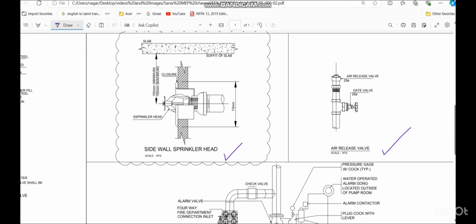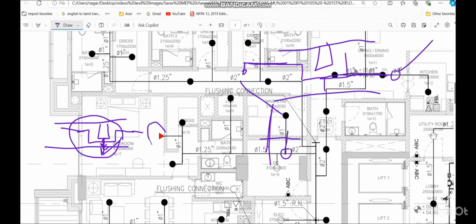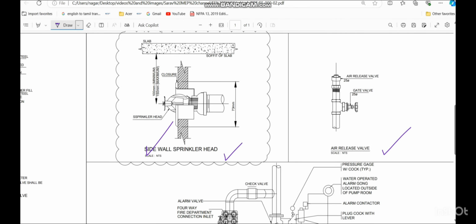Then coming to the next one, we have sidewall sprinkler installation. So in our project, we have sidewall sprinkler. As I told, if for each bedroom we don't have the ceiling, so there we have provided the sidewall sprinkler in the wall. So coming to the sidewall sprinkler, the rule for this like this, you can see the slab. So from the slab to the center of the deflector, we have to follow minimum 100 mm, maximum 150 mm. So this is for the sidewall sprinkler head.